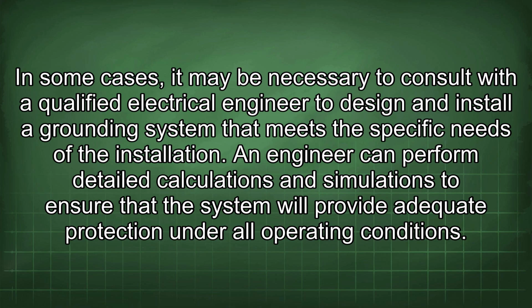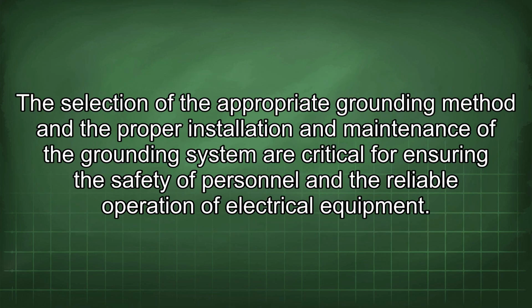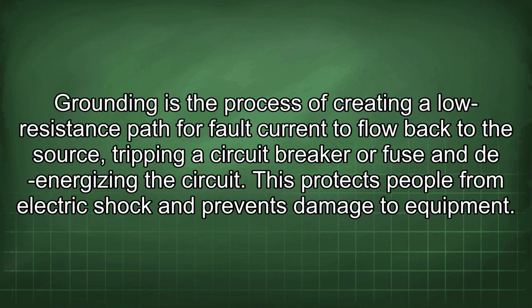An engineer can perform detailed calculations and simulations to ensure that the system will provide adequate protection under all operating conditions. The selection of the appropriate grounding method and the proper installation and maintenance of the grounding system are critical for ensuring the safety of personnel and the reliable operation of electrical equipment. Grounding is the process of creating a low-resistance path for fault current to flow back to the source, tripping a circuit breaker or fuse and de-energizing the circuit. This protects people from electric shock and prevents damage to equipment.